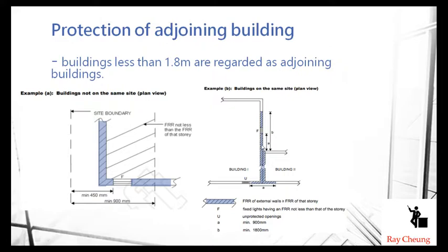You can see the blue highlighted requirement — at least 900 millimeters. From the adjoining building, if you have a fixed light opening, it should also have protection with the so-called FRR — fire-resistance rating. The protection should not be less than the specified value. Within 1.8 meters, the wall must be protected to prevent fire from spreading to another building.